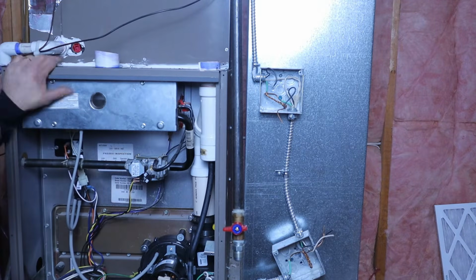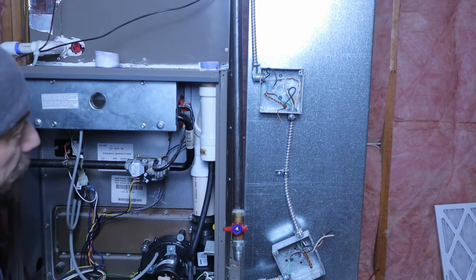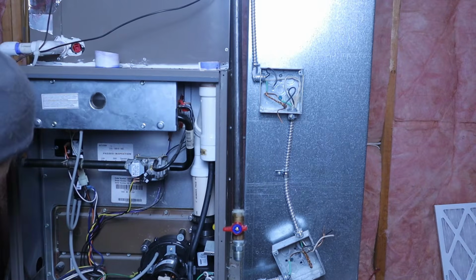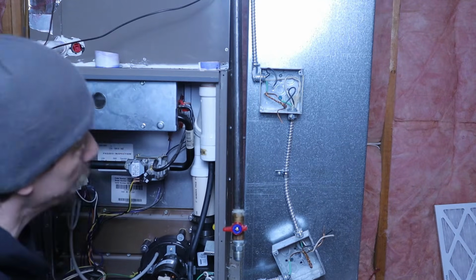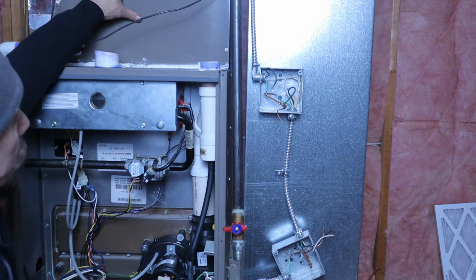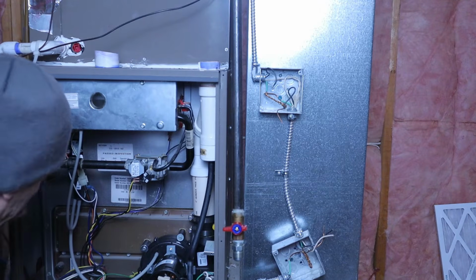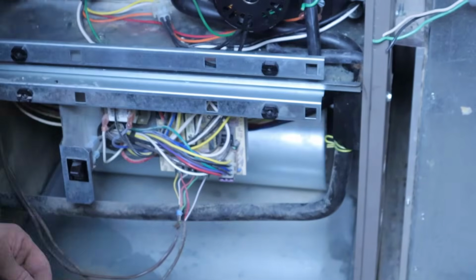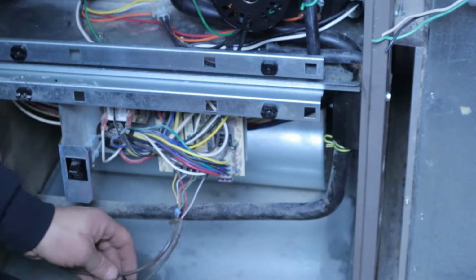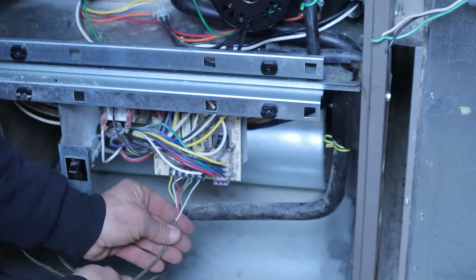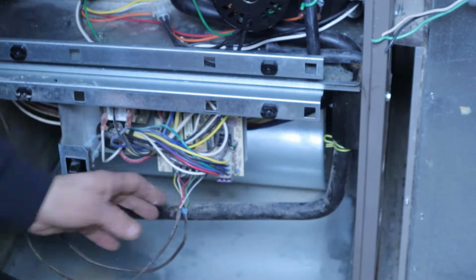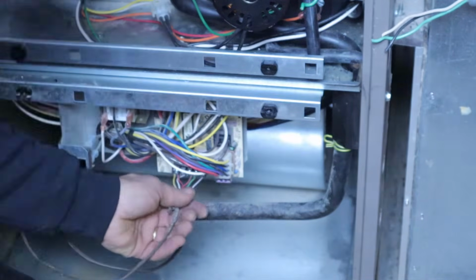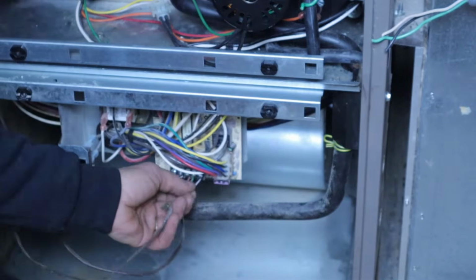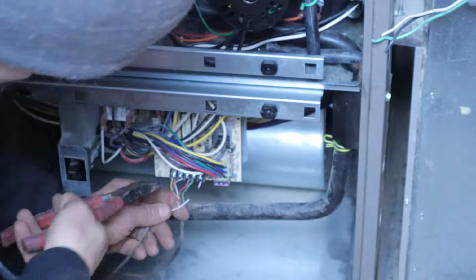All right, so we got our flue pipes disconnected. We got our PVC drain disconnected, electricals disconnected. Now we gotta do the thermostat wires. So we got heating and cooling here. This is our AC coil. So we'll have 2 wires, thermostat wires coming in. All right, so we got our 2 wires here, the red and white. That's from our condensing unit outside. And that's hooked up to the Y and the common. So we'll cut that out.